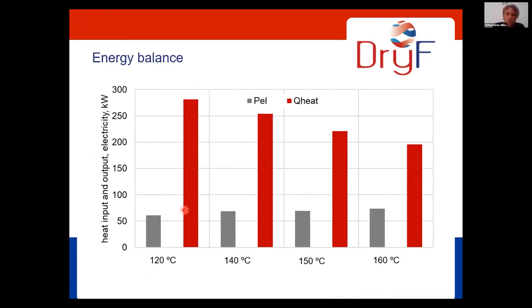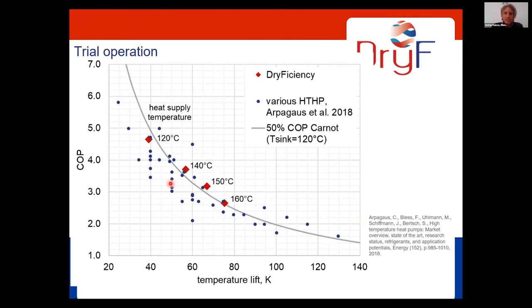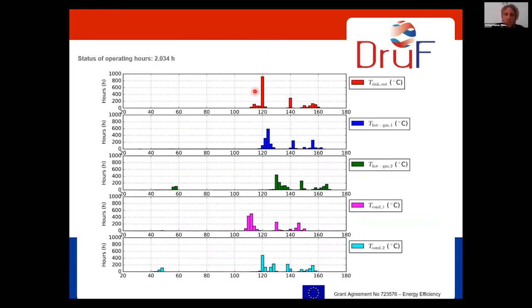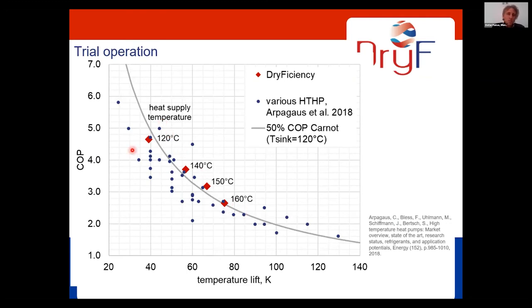You can make a calculation to find out the COP, but Veronika made this on another slide here. Here you see the temperatures we operated on. The 160 degrees was the target. We proved that it works well, but the energy consumption is quite high, and we pay much more for the electricity compared to AGRANA. So most of the time we operated at 120 degrees sink temperature. And when we compare the COP to market available heat pumps, we see that the DryFiciency heat pump performs quite well and additionally provides higher temperatures than market available ones.